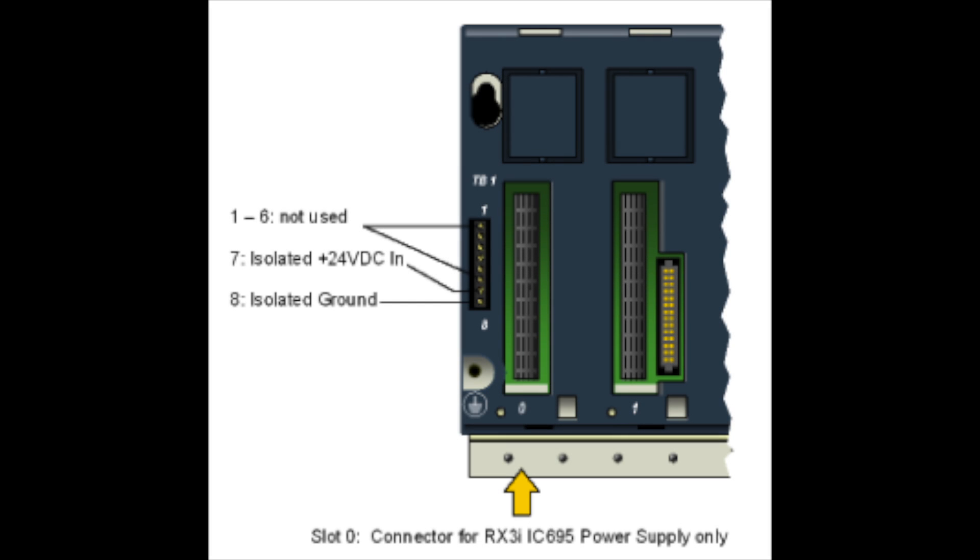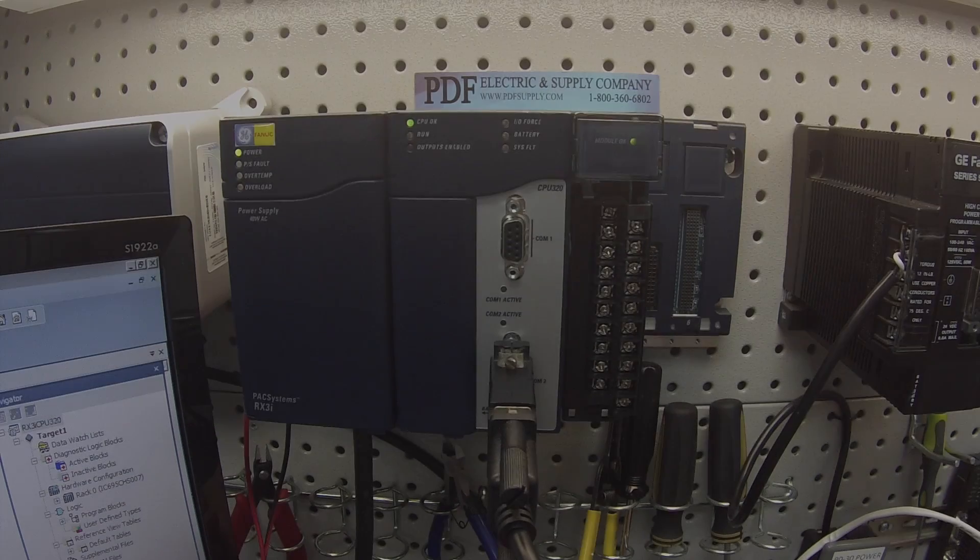To the left of the power supply, there's a terminal strip on the rack that's labeled TB1. The bottom two screws are the positive and the negative leads for the 24 volt power supply. The very bottom screw is the negative and the screw second to the bottom is positive.